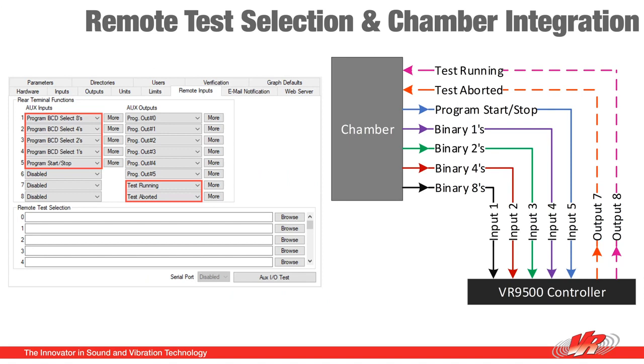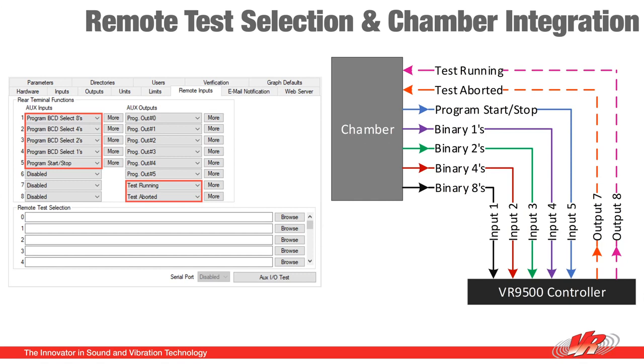You can also use the remote I/O as an interlock between a chamber and a controller. This is most useful when you're running shake and bake. So I have a chamber on top of my vibration table. When my vibration aborts, I can send an output to the chamber that tells the chamber to bleed to ambient. This prevents a whole bunch of thermal cycling from being done to a product that is not being shook. The same could be done the other way, that if the chamber aborts for any reason, it sends a signal to the controller and tells it to stop or pause the test.